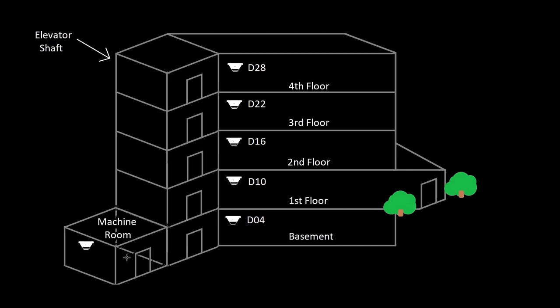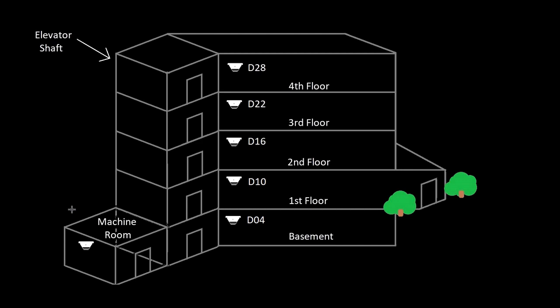Because sometimes you have a smoke detector in the machine room, in the pit, and the shaft. And for the machine room, the pit you'd send it maybe to the alternate floor assuming there were no basement. But for the shaft you would send it to the main floor and you'd flash the hat, and so then you need the two differentiating machine room hats. If that doesn't make a lot of sense right now, don't worry about it, I probably shouldn't even have mentioned that yet.